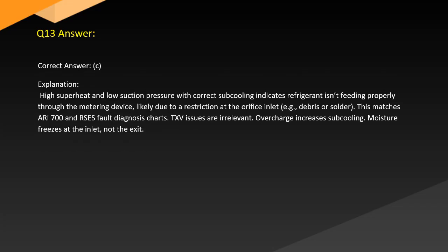Answer. Correct answer: C. Explanation. High superheat and low suction pressure with correct subcooling indicates refrigerant isn't feeding properly through the metering device, likely due to restriction at the orifice inlet, e.g. debris or solder. This matches ARI 700 and RSES fault diagnosis charts. TXV issues are irrelevant. Overcharge increases subcooling. Moisture freezes at the inlet, not the exit.